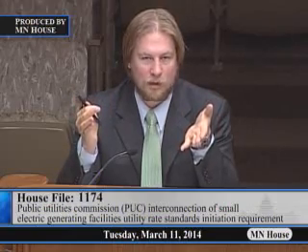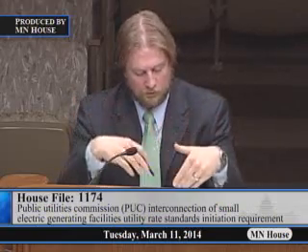And so what we're trying to do here is, if you're trying to put on a cogen facility where you're not going to touch a transmission system, you're putting on a couple megawatts, and the overall substation minimum loads are, say, 20 MVA, there's no practical possibility of that power getting onto the transmission system. You should be able to interconnect that power much more easily and readily. And also, by requiring these additional criteria, they have to account for the savings because you're not having to draw down as much power from the transmission system when it's congested. That should be put into the tariff that is paid for that DG power.